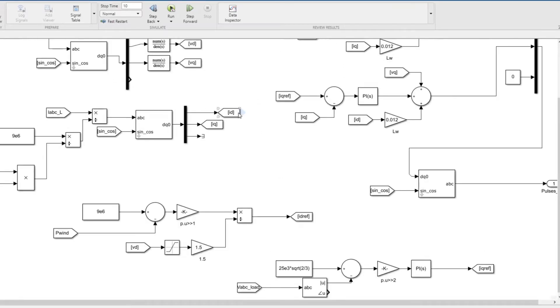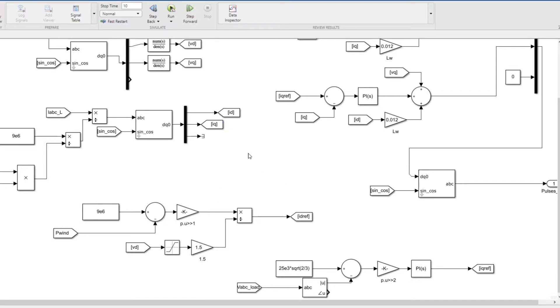If you control the id, you're controlling the active power. If you control the iq, you're controlling the reactive power injection from the unit. The battery has to generate the rest of the power - 9 megawatts is what we need, so that minus wind is the battery power.